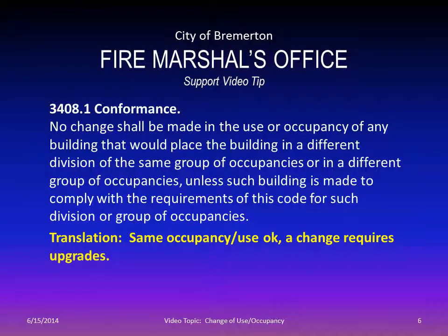So, kind of paraphrased here, no change shall be made in use or occupancy of any building that would place it in a different division of the same group of occupancies or in a different group of occupancies. Translation: same occupancy is okay, same use is okay. If there's a change, it's going to require upgrades most likely.